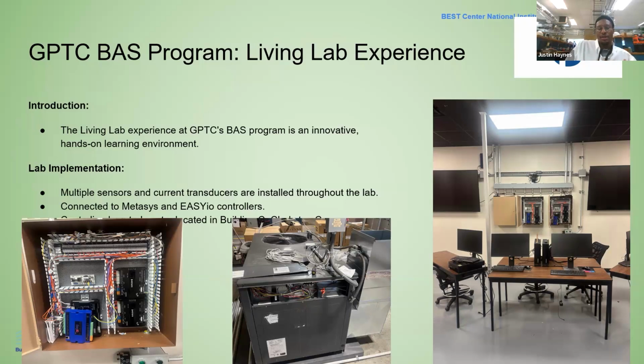Another cool thing about that lab is it has a taller ceiling than any other room in our building. Therefore, as many of you know, you would need to stack up multiple temperature sensors. For that room, we have 4 stacked up so that we can average out the temperature.